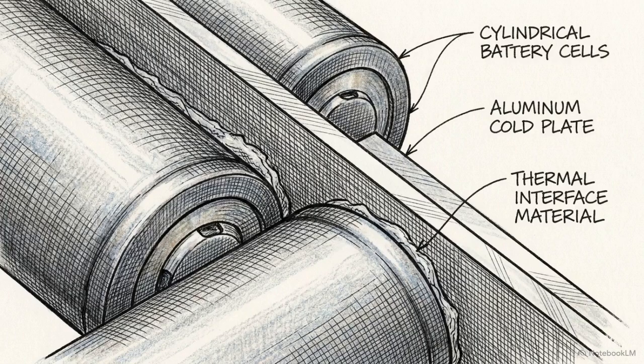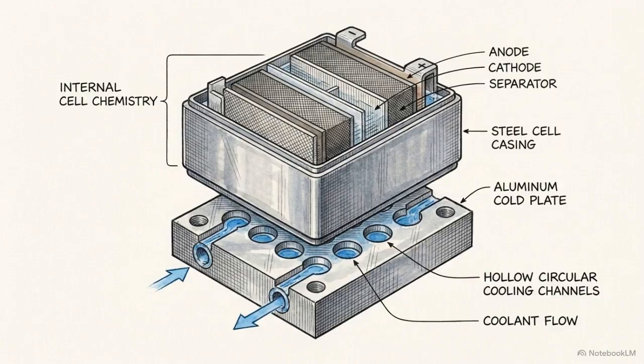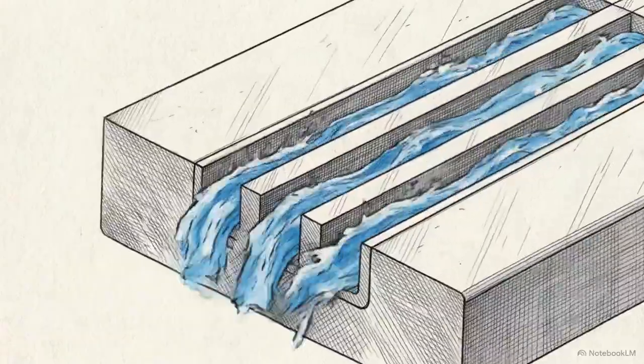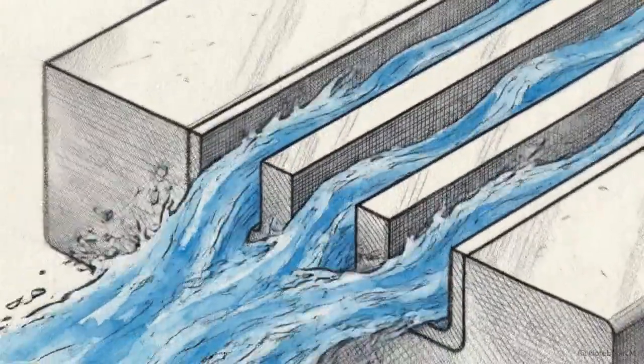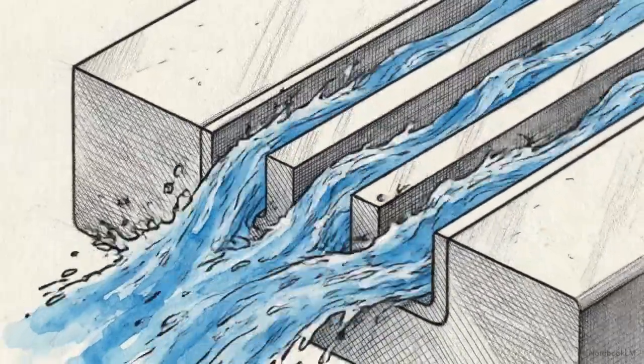The direct thermal interface between the battery and the cooling system is the cold plate. This is an extruded aluminum block sitting directly beneath or between the battery cells, engineered to pull heat away from the battery casing. The challenge is routing liquid coolant through the internal microchannels of this plate fast enough to extract that heat before the aluminum becomes saturated. This diagram shows the two primary approaches to routing fluid, a single serpentine flow path on the left and a split parallel flow path on the right.